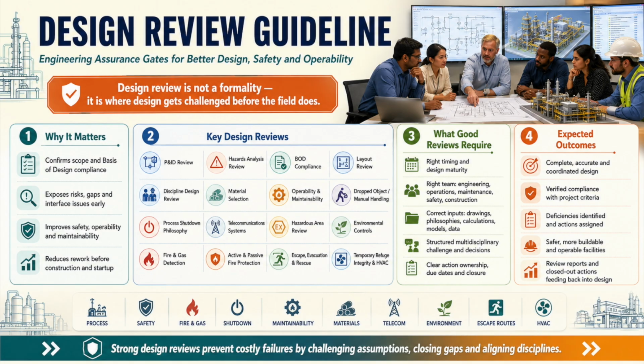Finally, temporary refuge integrity and HVAC reviews challenge whether protected occupied spaces remain habitable during major accident events. You examine external walls, decks, doors, penetrations, ductwork, dampers, internal segregation, structural support, passive fire protection, smoke ingress, gas ingress, detection, isolation, shutdown, emergency operation, recovery, redundancy, maintenance access, equipment replacement, manual initiation, emergency power, and interaction with fire and gas systems. You review both normal HVAC operation and emergency modes. You test whether the system can isolate, maintain integrity, prevent contamination, support occupancy, and recover after shutdown.